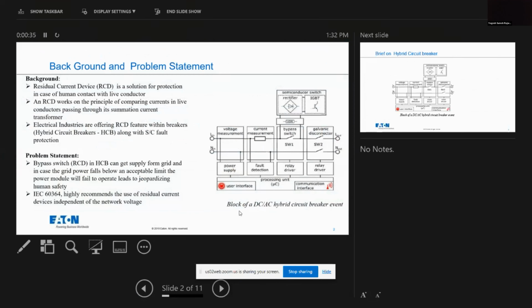The background is that in the electrical sector, there is a residual current device. This device is mostly used to safeguard humans if there is a live conductor. If there is a ground and a live conductor comes in contact, this device will immediately detect it and open the contact, so the human is safeguarded. The principle of this RCD on the live conductor is that it has a summation transformer which gives a signal to the relay, and the relay will open.